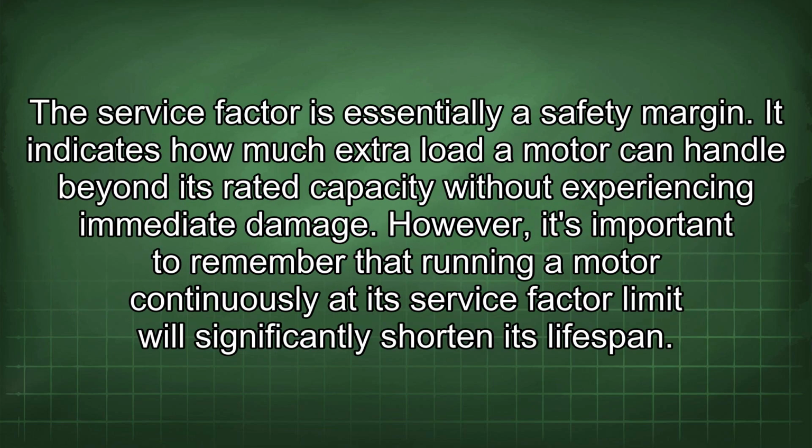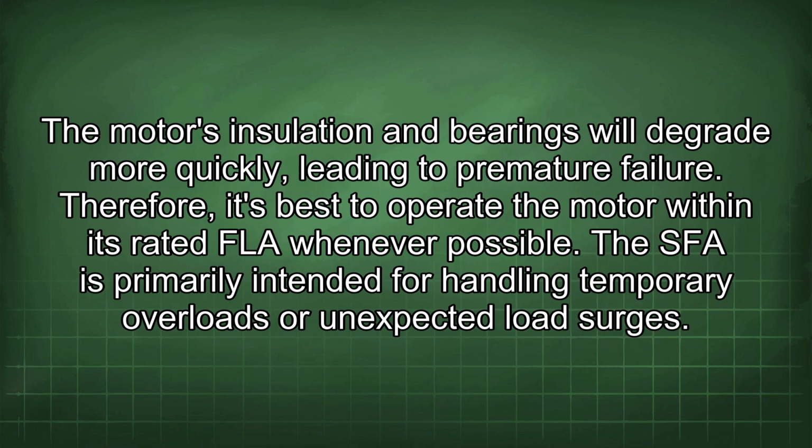The service factor is essentially a safety margin. It indicates how much extra load a motor can handle beyond its rated capacity without experiencing immediate damage. However, it's important to remember that running a motor continuously at its service factor limit will significantly shorten its lifespan. The motor's insulation and bearings will degrade more quickly, leading to premature failure. Therefore, it's best to operate the motor within its rated FLA whenever possible.